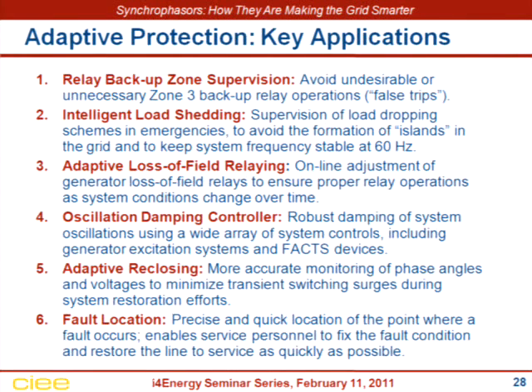Loss of field relaying is a generator-specific thing. The field is the excitation in the armature that provides the magnetic field for the generator to provide power. And sometimes it loses its field energization, and it's hard to detect. But also, it'll do that under different conditions, so you want to be able to adapt to those different conditions.